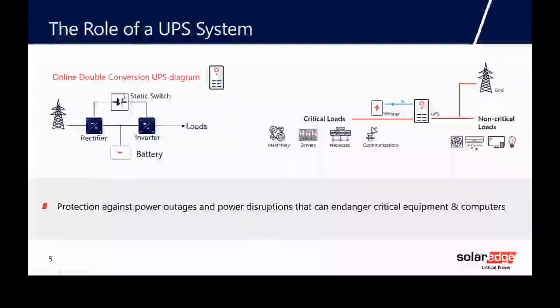And then finally, we have a static switch. That's there as a backup, as a bypass. If the inverter is overloaded or fails, the static switch will close without any break, so the load will continue to operate in bypass mode.